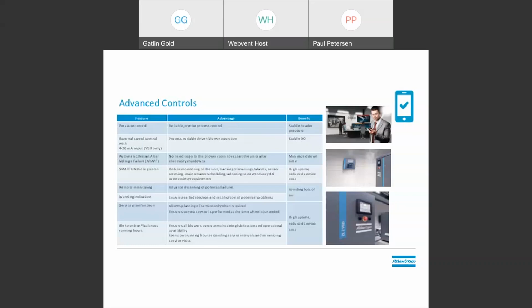With advanced controls connected remote monitoring, we have the ability to see more information than ever before. The controls can also enhance the unit's reliability automatically by monitoring key parameters and modifying them to avoid potential problems. Multi-unit control can also be used to dictate the most reliable and efficient setup, which can automatically keep the hours similar between the units so that when you have a service technician come out, they can service all of your units at one time. This equals less trips, less cost. We can also enhance the reliability by automatically switching between units if any of them have issues.